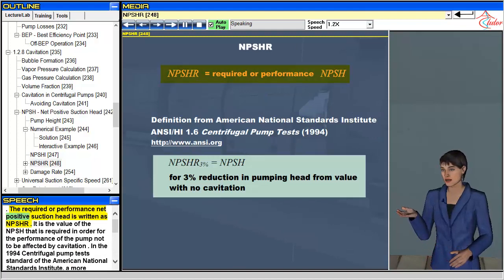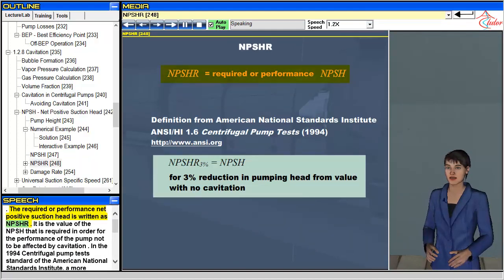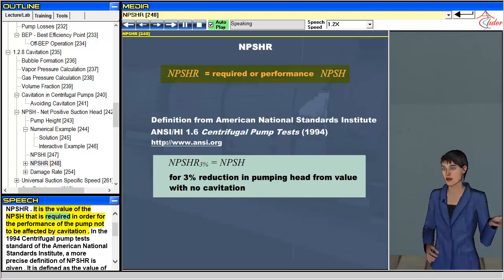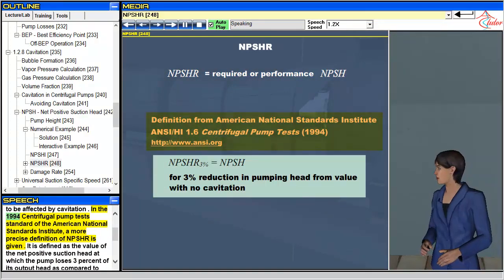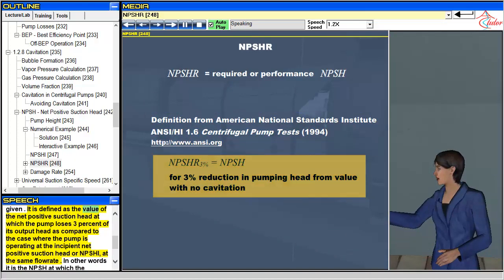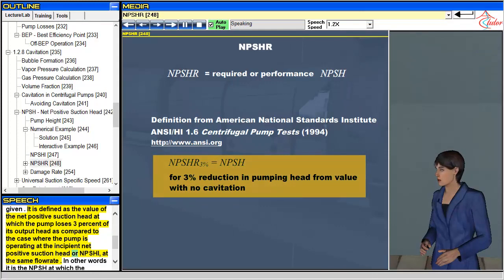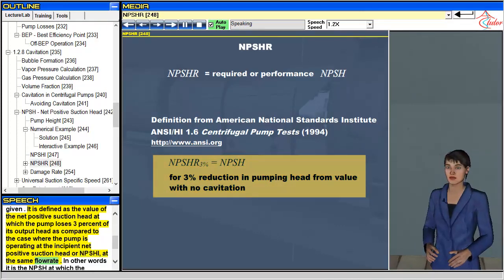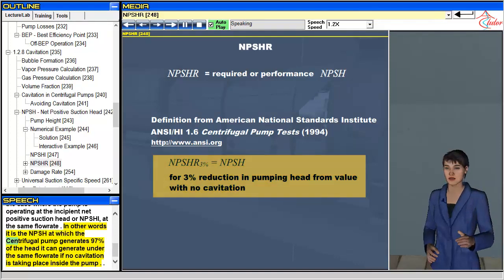The required, or performance, net positive suction head is written as NPSHR. It is the value of the NPSH required in order for the performance of the pump not to be affected by cavitation. In the 1994 centrifugal pump test standard of the American National Standards Institute, NPSHR is defined as the value of the net positive suction head at which the pump loses 3% of its output head compared to the case where the pump is operating at the incipient NPSHI at the same flow rate — in other words, the NPSH at which the pump generates 97% of the head it would generate with no cavitation.